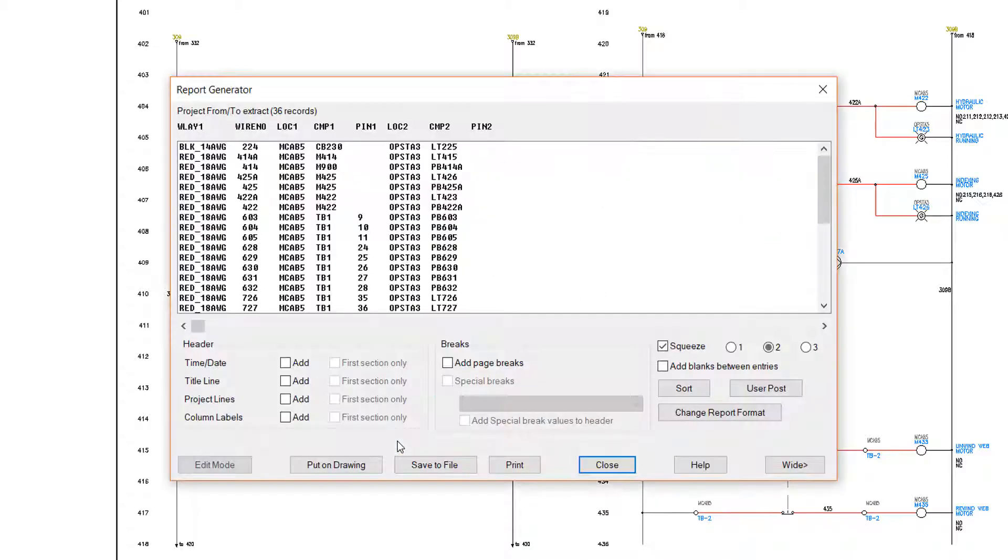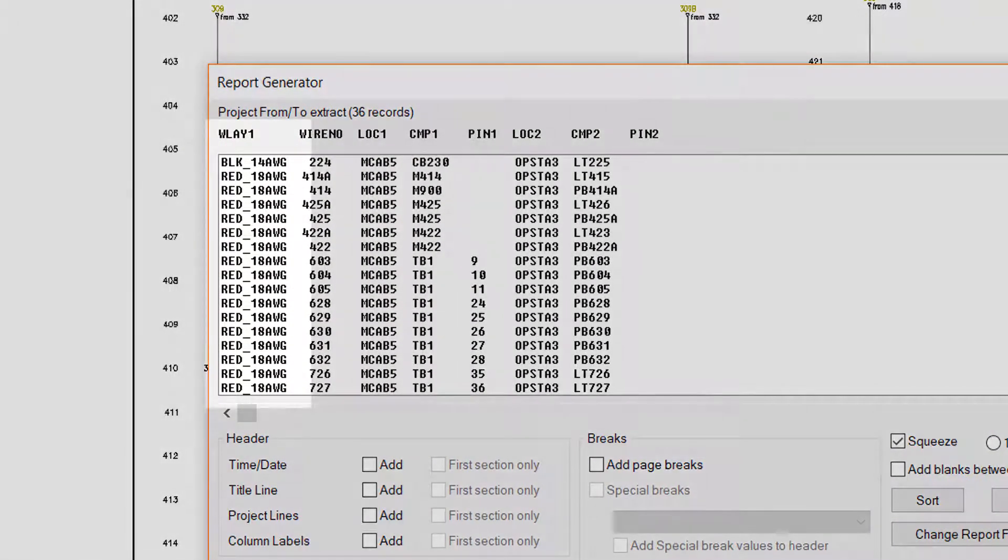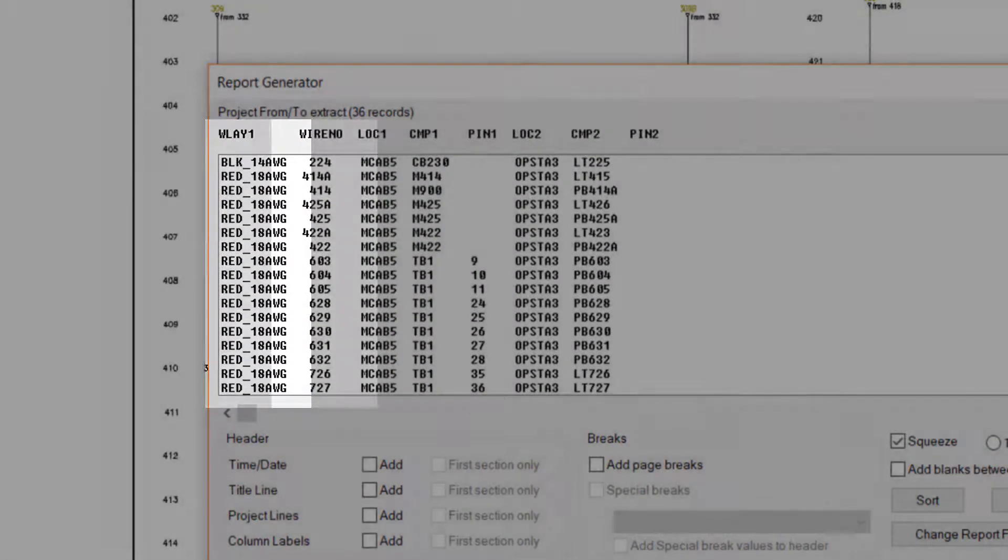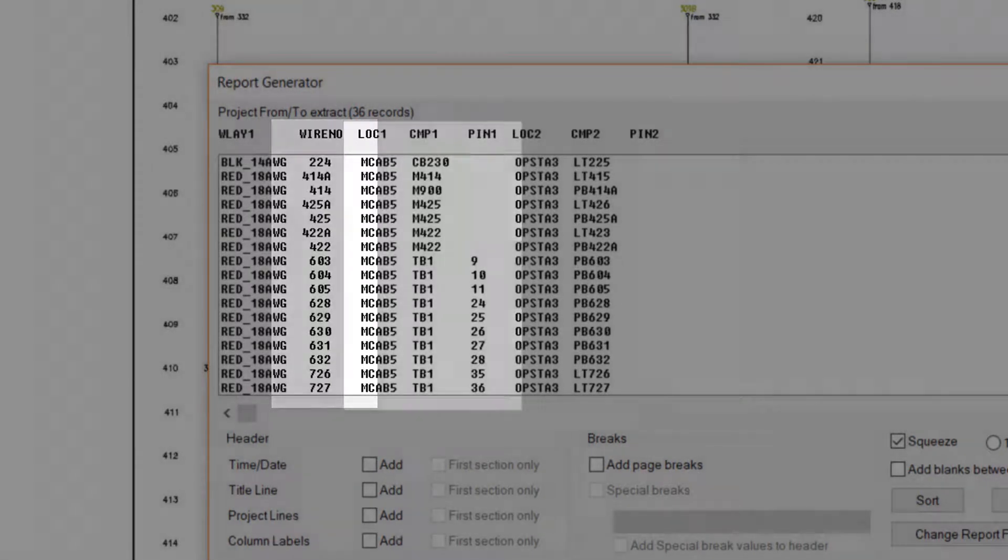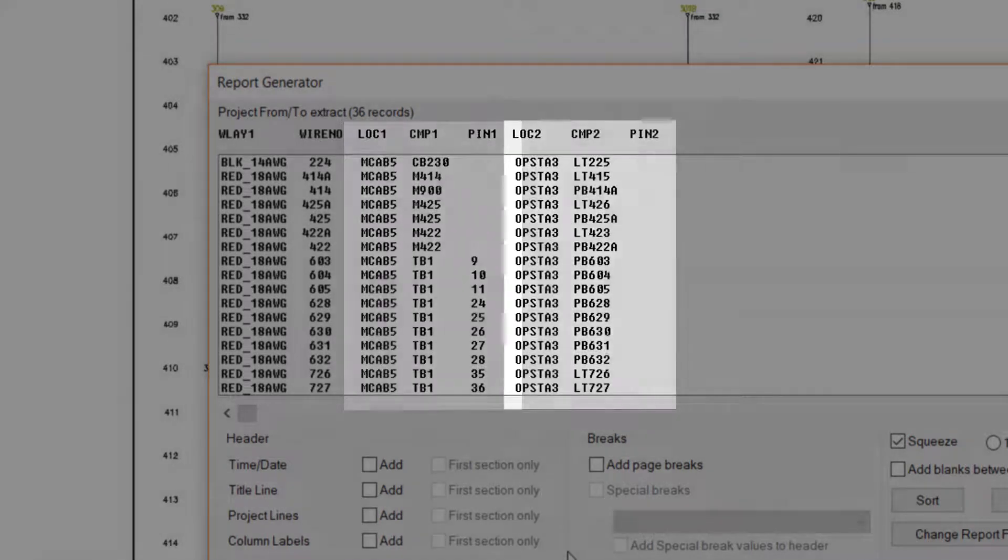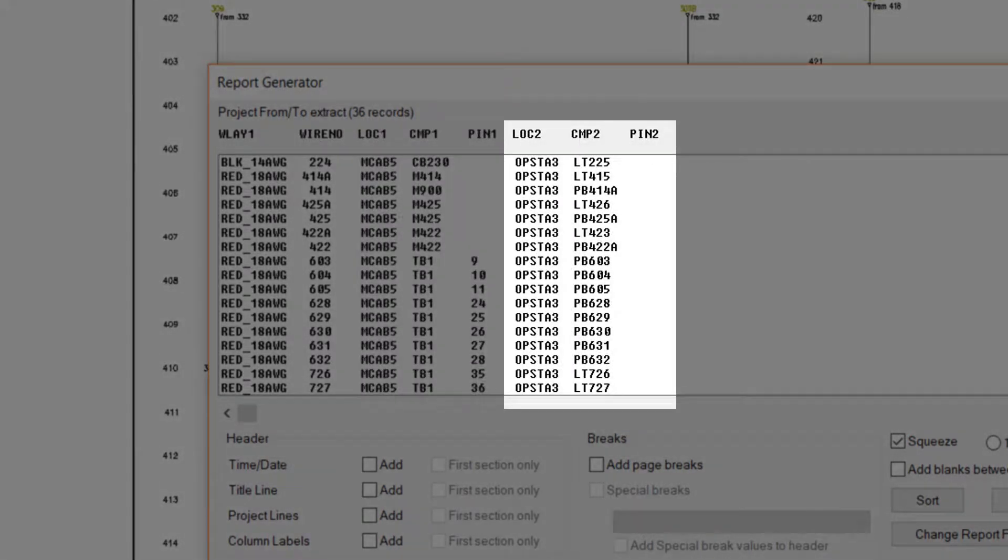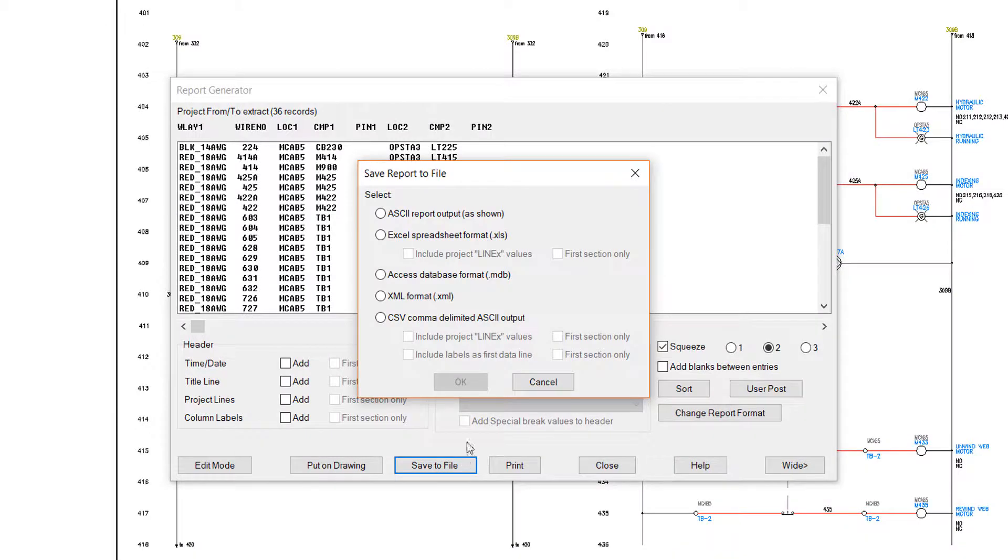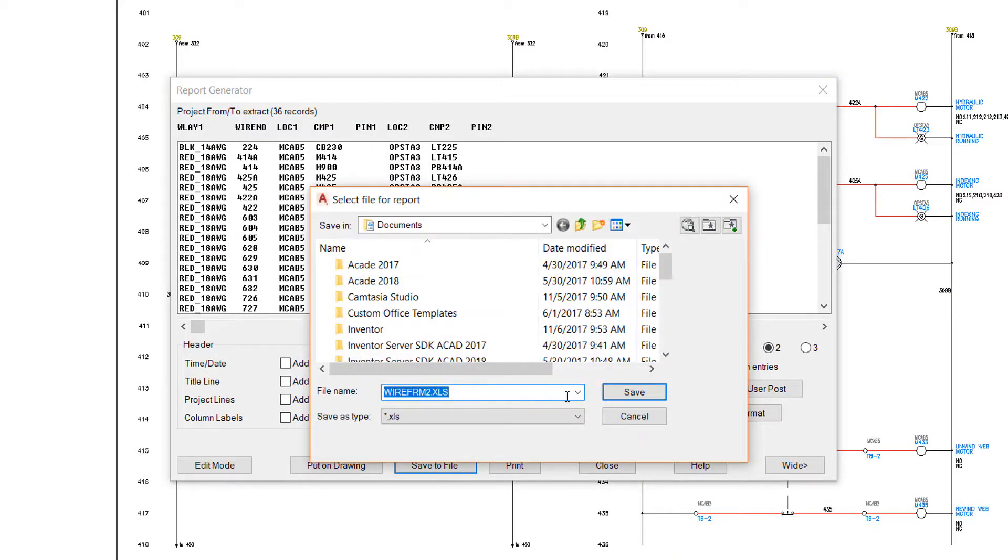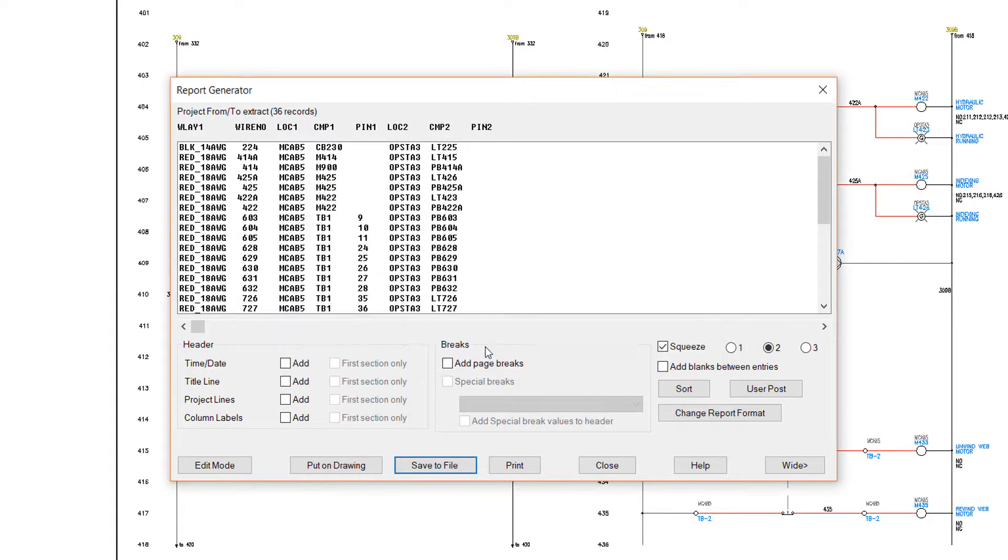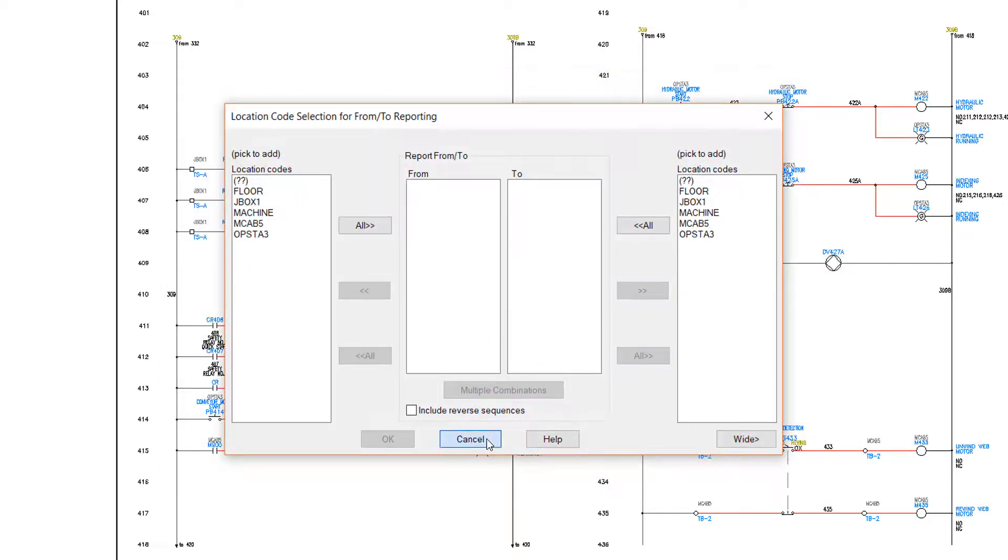The resulting wire list shows all details needed for this conduit connection. Starting with the wire type and gauge, the wire number, the wire starting location, component, and pin, and the wire ending location and pin are listed. As usual, with AutoCAD Electrical, you can save the report as a table on the drawing or save it to an external file.